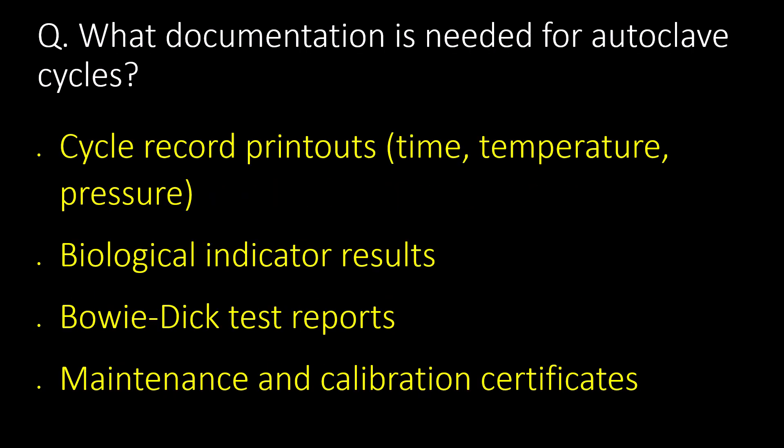What documentation is needed for autoclave cycles? Cycle record printouts showing time, temperature, and pressure; biological indicator results; Bowie-Dick test reports; and maintenance and calibration certificates.